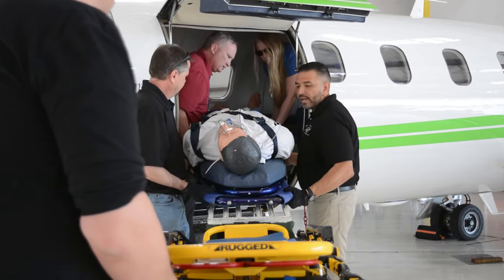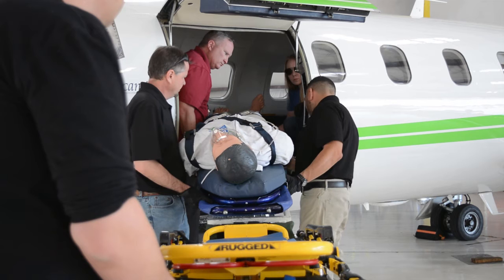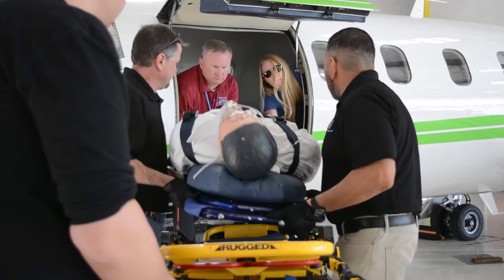One thing I wanted to point out, there's some locking mechanism that's underneath. If you tend to get caught here with your patient and it doesn't seem like you're going forward at all, there's actually a locking mechanism that's here midway down the ramp. That always needs to be flat. If it's facing upward, you're actually going to stop the sled from moving forward.